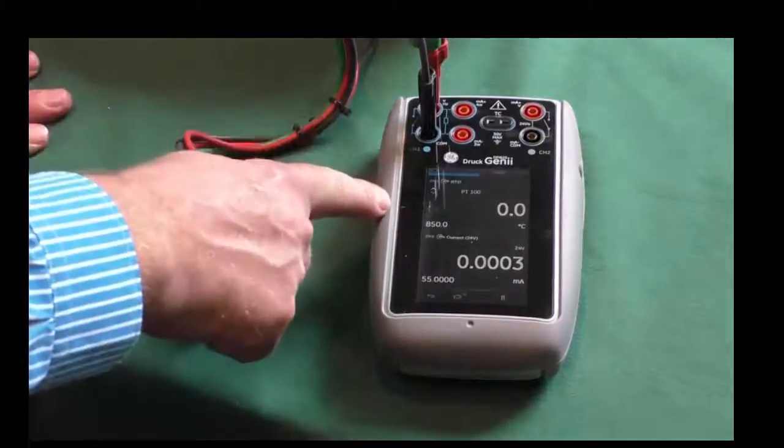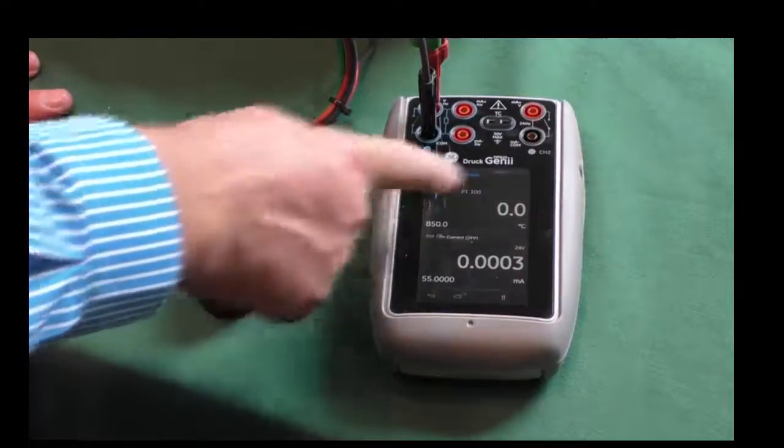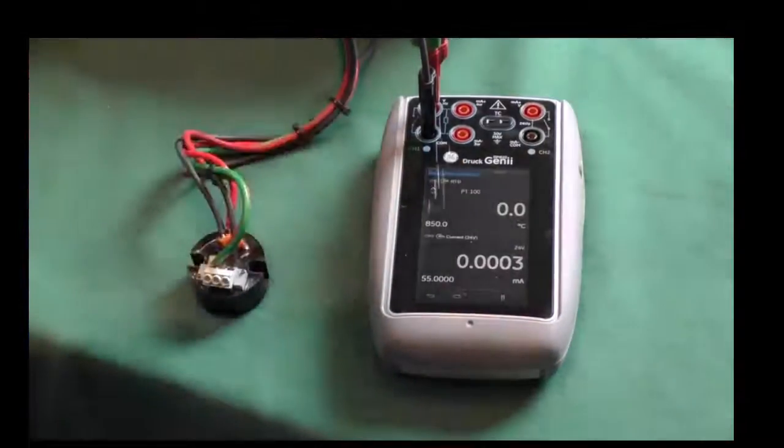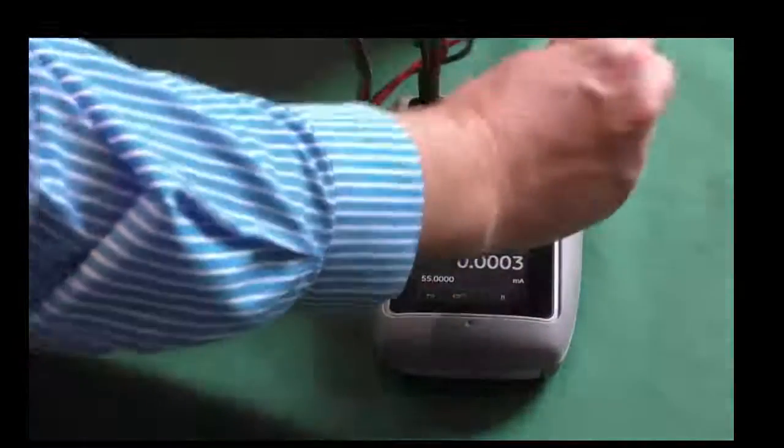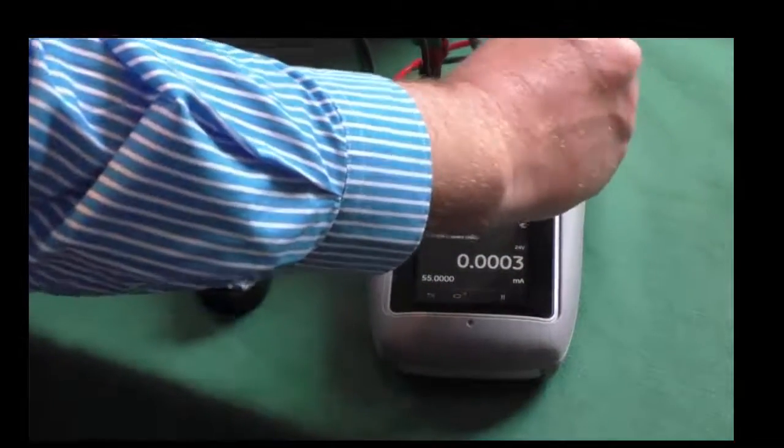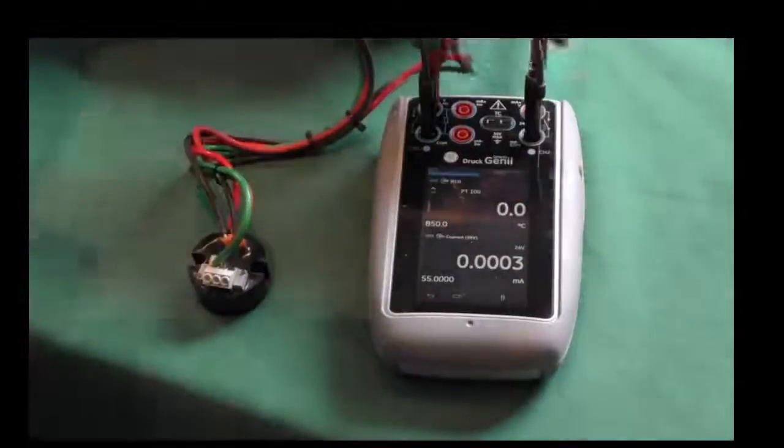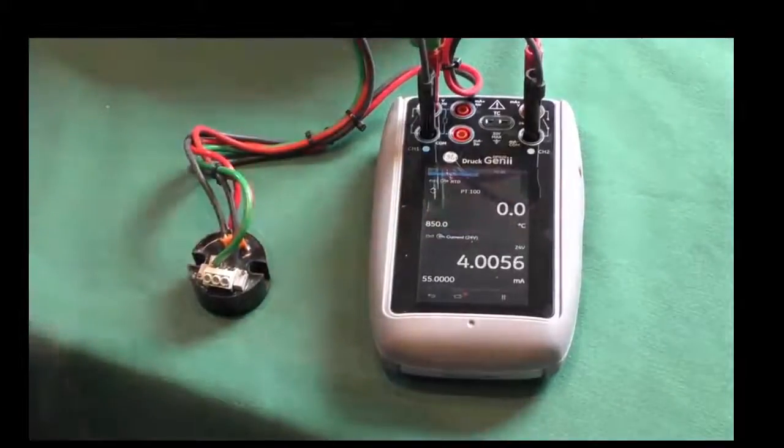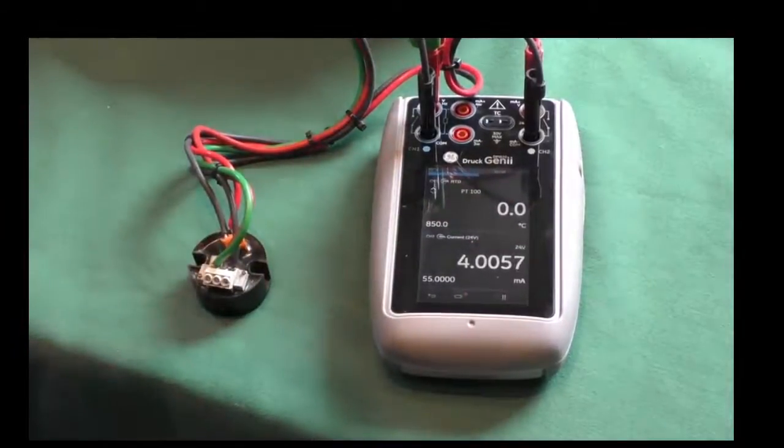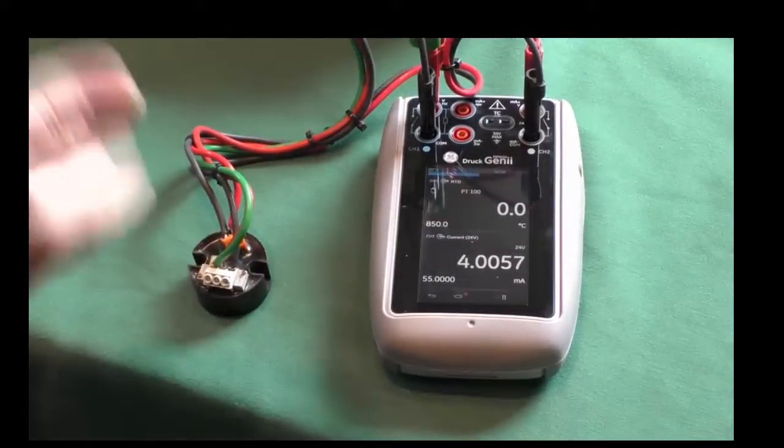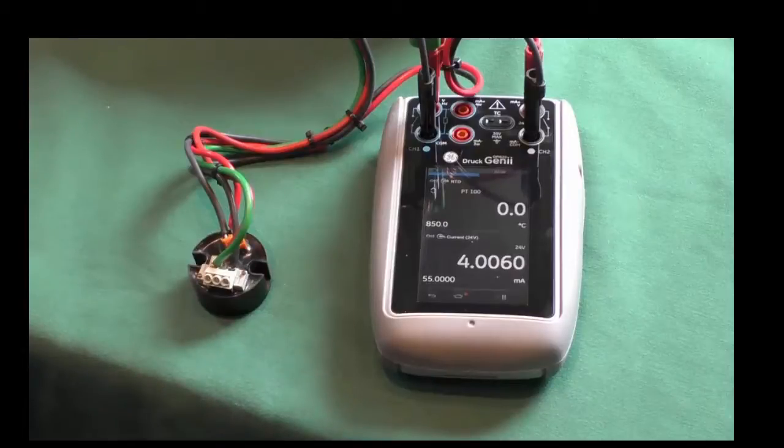So if we look on here, channel 1 is degrees C. Now it's a transmitter, so as you remember before, we've got 24 volts supply on channel 2. Connect that in, and straight away, 0 degrees C is 4 milliamps. So this is PT100, 0 to 100 degrees C.